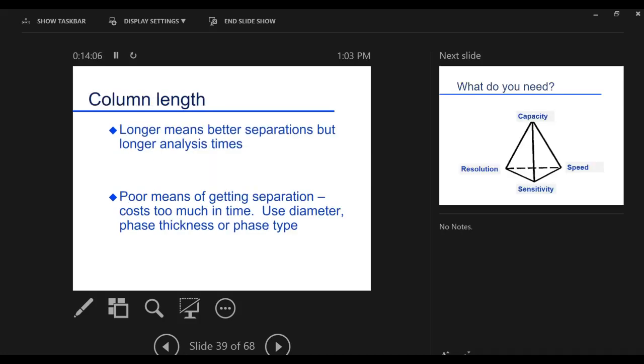The idea, well, how long should this column be? I think I said they run anywhere from, you know, that long to 100 meters. So as you might expect, the longer the column, the more efficient. But every time I double the length, I double my analysis time. If I go from 1 meter to 100, it takes me 100 times longer to get my data. So not a good deal. It's not an efficient way to get separation. You want to use short column. You want to get the shortest column that you can and still get your separation. Again, it saves time.